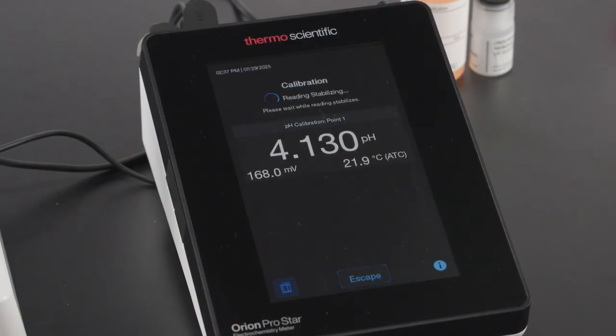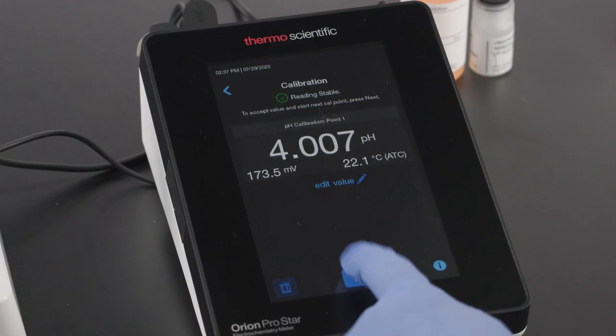A spinning progress indicator and the message Reading Stabilizing display while the electrode senses pH and reads the buffer temperature. When a green check and the Reading Stable message displays, the Orion ProStar meter has automatically recognized the pH buffer and assigns the correct pH value for the buffer at the measured temperature. Tap the Next button to accept the first calibration point.